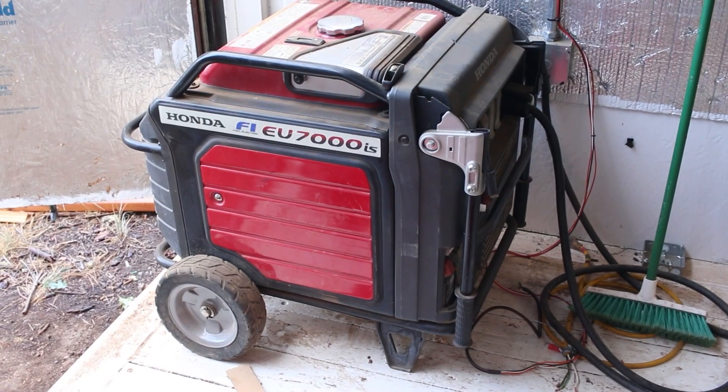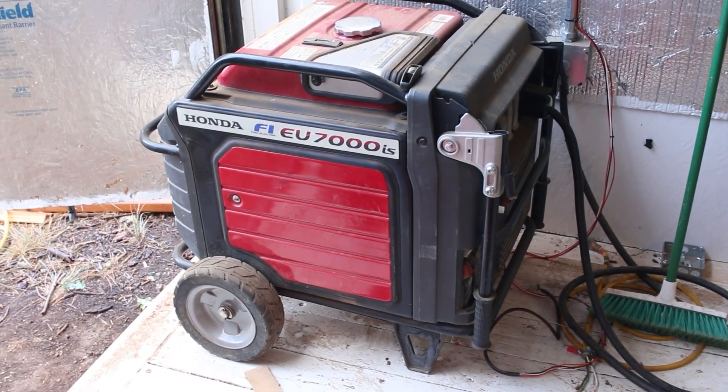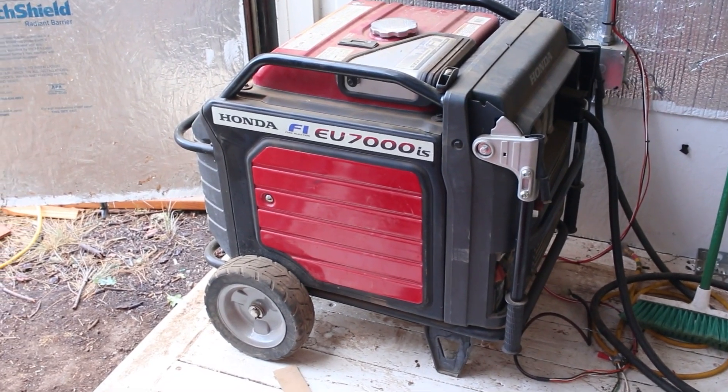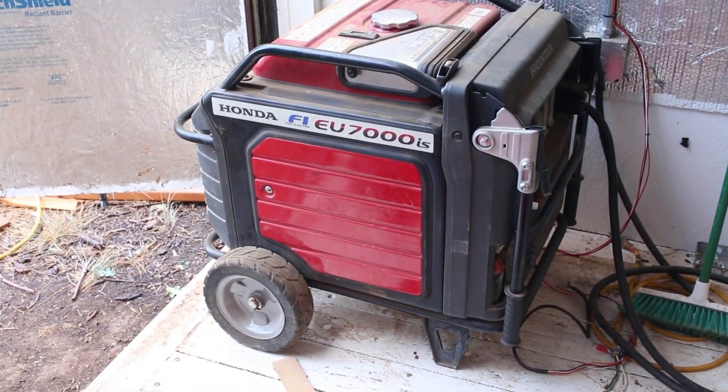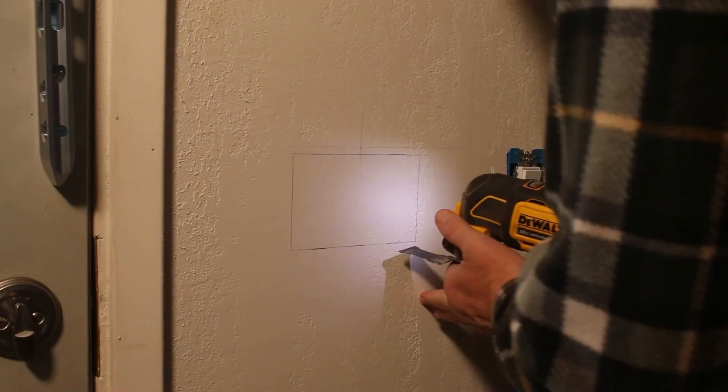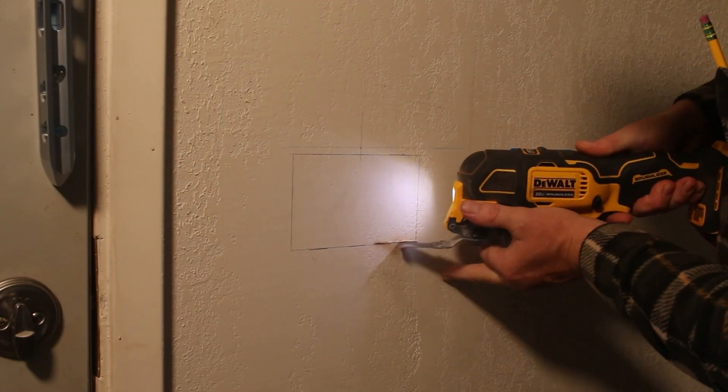I was able to find a breakout cable for my generator and what it does is it bypasses the front panel on the generator which has a key to enable it and a push button to start it. The breakout cable's got four wires. Two of them are to enable, so you short those together and it enables the generator. The other two, short them together momentarily and that starts the starter. In a few seconds you release it and then the generator's running. To turn it off all I have to do is release these two and then the generator's off. Pretty easy to do with a couple of relays.